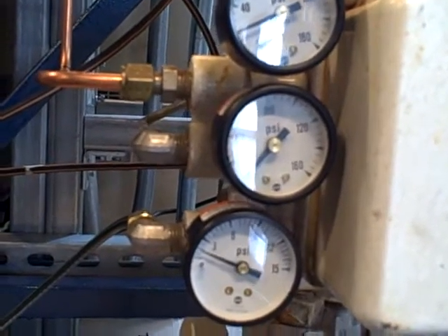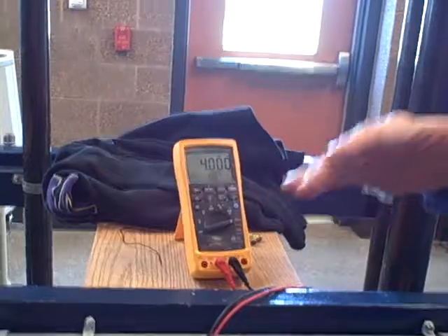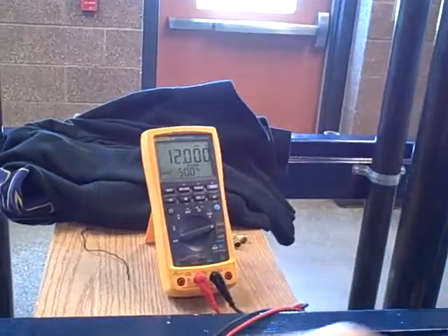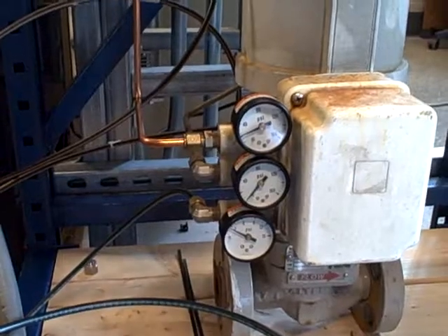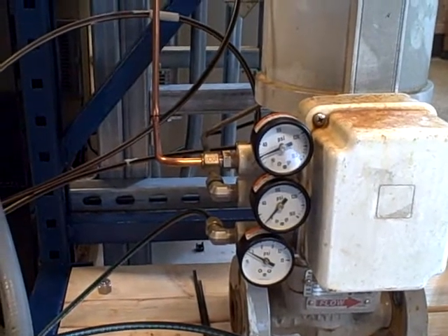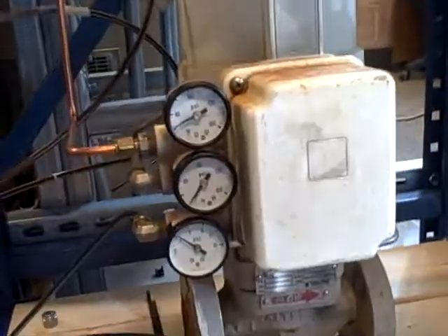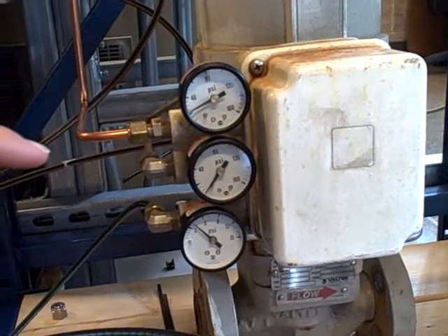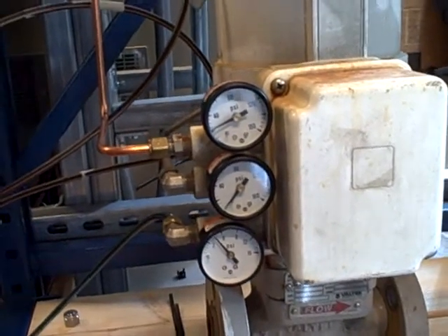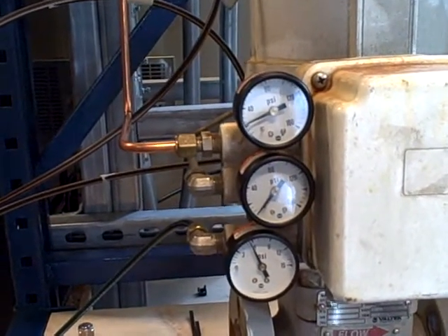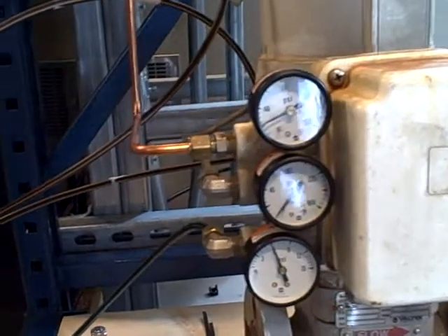What you're seeing there is the output of the distributed control system controller integrating up and down on the output signal. So it's ramping up and ramping down, and we can see with the camera here how the update time of that control system is finite. As I put a larger signal into our loop calibrator, we can watch the needle on that gauge go up in steps. Those steps, those increments that you see, that update time is the scan rate of our control system. You can see with a digital control system like the Emerson DeltaV, it is not instant. It actually does take some time to scan through.